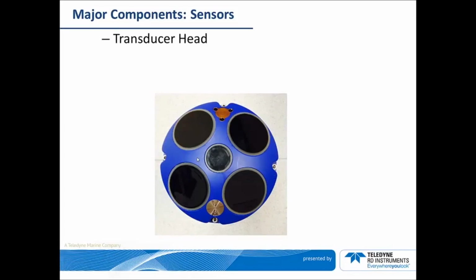At the transducer head, we will find the beams. Again, the 5th beam or the vertical beam, which is the one in the center, is optional. And then there's the pressure sensor, which the Sentinel V uses to measure transducer depth and has a standard rating of 30 bars. And there's the temperature sensor, which along with the depth and salinity values the Sentinel V uses to estimate the speed of sound. Unlike the older generation workhorse ADCPs, the pressure sensor and the temperature sensor come as standard with the Sentinel V.